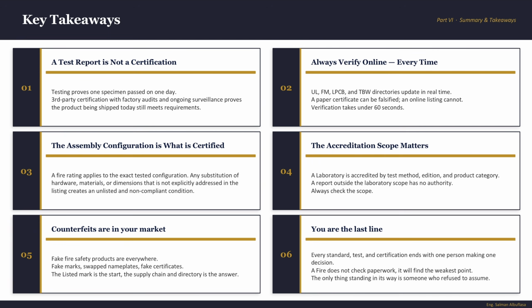Second, always verify online, every single time. No exceptions. No matter how swift the application is, do not approve without checking online. The papers can be faked, the database cannot. The UL, FM, or LPCB databases are all live, all real time, and it takes only 60 seconds or even less to check. And check it on the day you make the decision, not when the submittal came in. And third, the assembly configuration is what is certified. What that means is not the name, not the brand, but the exact configuration that went into that furnace. Every material, every dimension, every component, every fixing detail. Change one thing not covered in the listing, and you have an unlisted product in your building full of people.